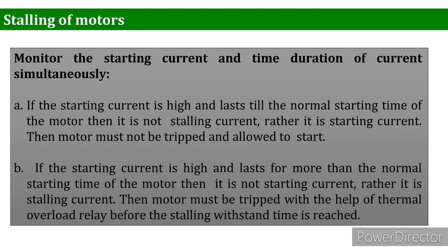The second condition monitors the starting current and the time duration of the current simultaneously. A: if the starting current is high and lasts till the normal starting time of the motor, then it is not a stalling current. Rather, it is a starting current, and the motor must not be tripped and must be allowed to start. B: if the starting current is high and lasts for more than the normal starting time of the motor, then it is not the starting current. Rather, it is a stalling current, and the motor must be tripped with the help of a thermal overload relay before the stall withstand time is reached.